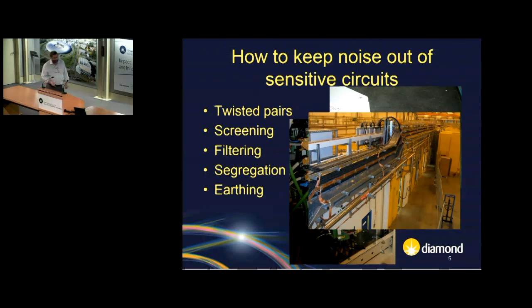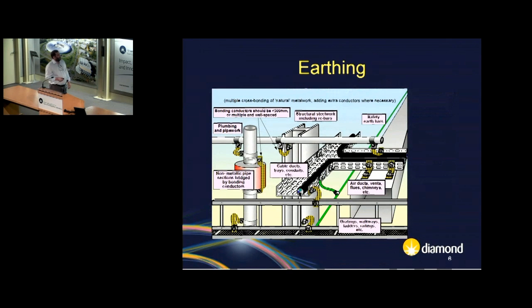This is an illustration from a description of the earthing system, and what it tells you is that everything is connected to everything else, all the extraneous metalwork. So we've got the walkway at the bottom, the cable trays, the structural steel. We also connect the reinforcing metal in the concrete storage ring. There's also lightning protection conductors and earth supplies that we bond into the system.